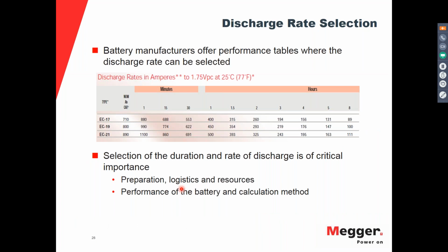I showed the connection and I showed the result, but there are a lot of things in between. You need to define your discharge rate. You need to select your discharge rate. We already mentioned that you need to use the tables, but you have several options there: 1 hour, in this case 1.5, 2, 3, 4, 5, 8 hours, and you even have minute options. It doesn't mean that you can use these interchangeably between tests, or that you can select one of these rates arbitrarily.